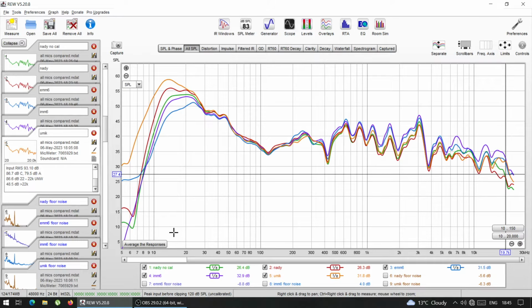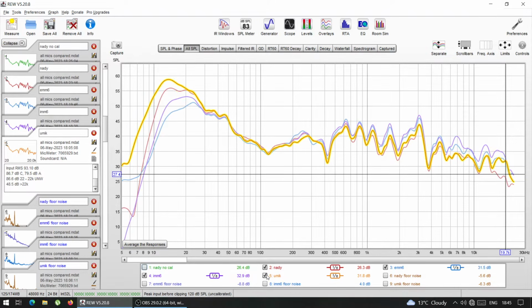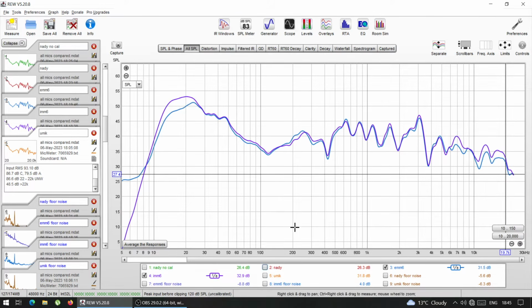So even if I take the same manufacturer, the Dayton one, so let's compare the EMM, the 3.5mm, and the IMM. Both of them have differences. They came from the same manufacturer, and both of them have calibration files. And as you can see, both of them measure slightly different, especially at the top end. 1 dB here, 1 dB there, and at the bottom end. However, if I just assume that this EMM that I bought secondhand is faulty, I'm just going to remove it, and I'm going to have this.